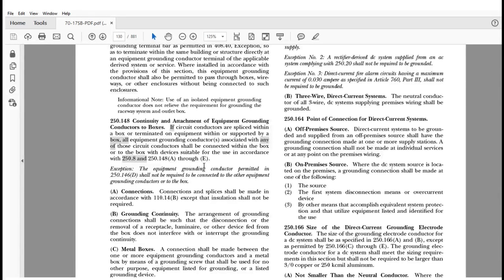All right, so this is a revision to 250.148 dealing with the continuity and attachment of equipment grounding conductors to boxes. Rather than paraphrase, let's just read the portion that I'm going to read here. It says, if circuit conductors are spliced within a box or terminated on equipment within or supported by a box, this is important, all equipment grounding conductors associated with any of the circuit's conductors shall be connected within the box or to the box with the device suitable for the use in accordance with 250.8. So 250.8 has been added to remind you of the proper terminations that have to be used. They give you guidance on terminations, so that was added in the 2017 to give you that guidance on where to go and say, yeah, okay, I understand you want me to make all these together, but give me some guidance on the terminations. Well, it does now, so that's great.